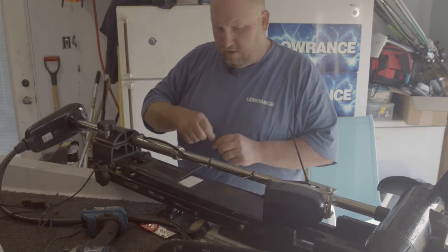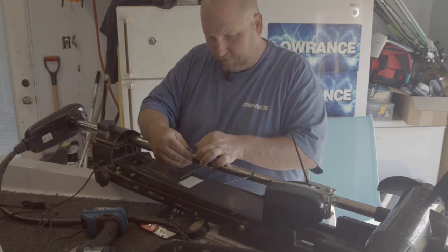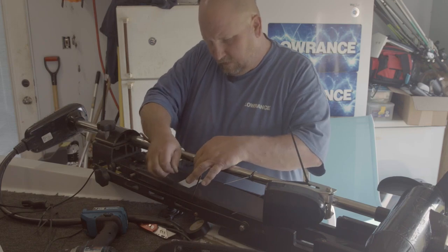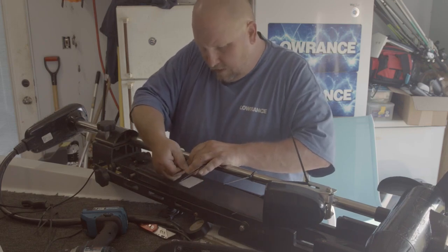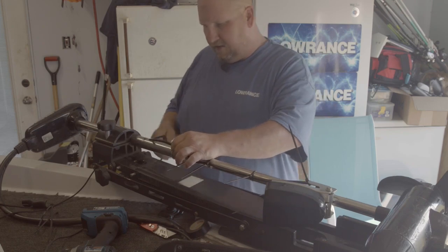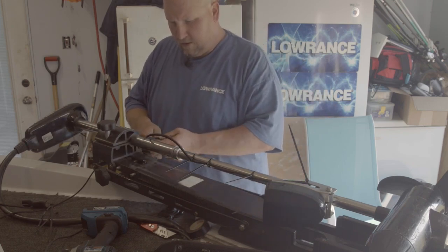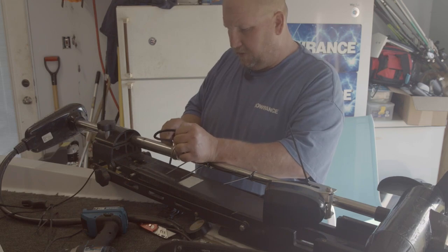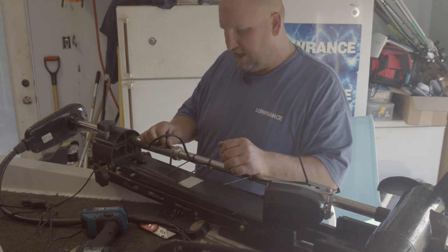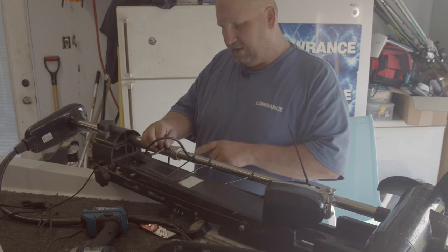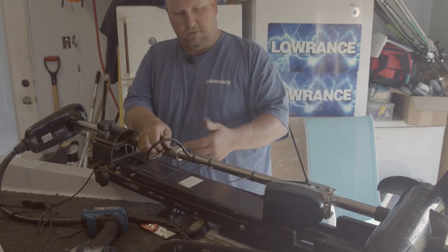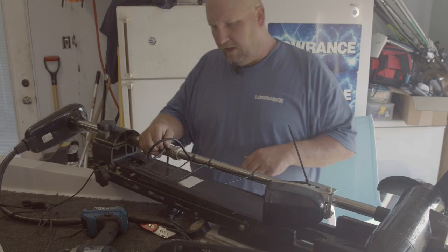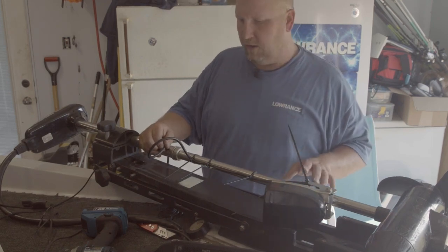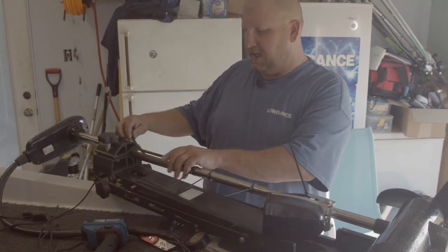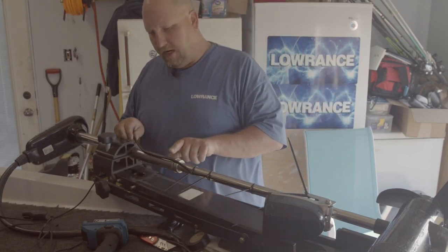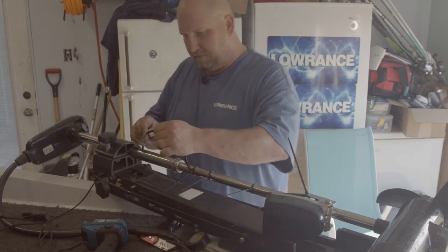I'm going to put one more here on the bottom. One of the most important things I need to do now is make a loop in the transducer cable like this. This loop allows the cable to spin all the way around the shaft whenever the foot pedal is worked. If I don't put a loop in here and just keep it straight, it's going to bind my cable and tear it.